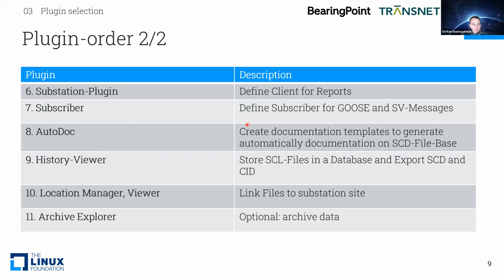actually, it's more or less finished from our side, and we can document the details in the Autodoc plugin, where we can create documentation based on templates completely automatically. We will go into that topic a little bit later. With the history viewer, it's possible to store those files in a database, version them, and also export the SCD and CID files.